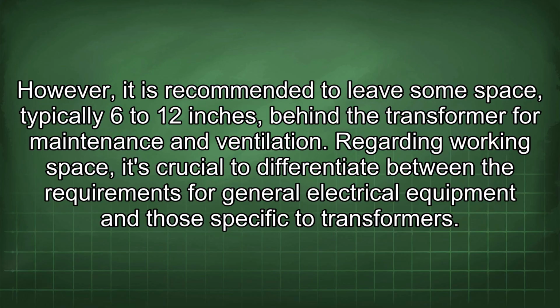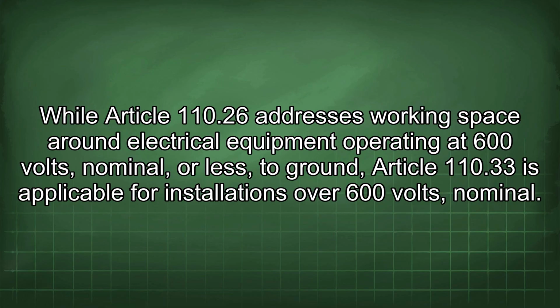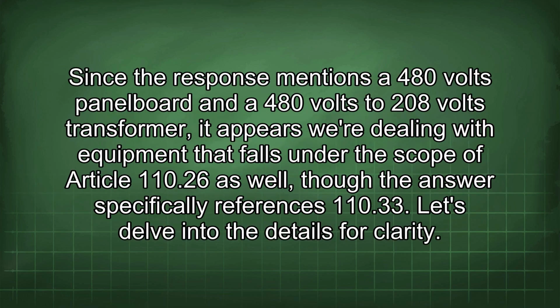Regarding working space, it's crucial to differentiate between the requirements for general electrical equipment and those specific to transformers. While Article 110.26 addresses working space around electrical equipment operating at 600 volts, nominal or less, to ground, Article 110.33 is applicable for installations over 600 volts, nominal. Since the response mentions a 480 volts panel board and a 480 volts to 208 volts transformer, it appears we're dealing with equipment that falls under the scope of Article 110.26 as well, though the answer specifically references 110.33. Let's delve into the details for clarity.